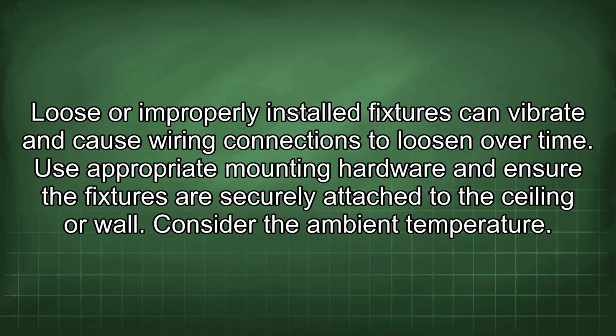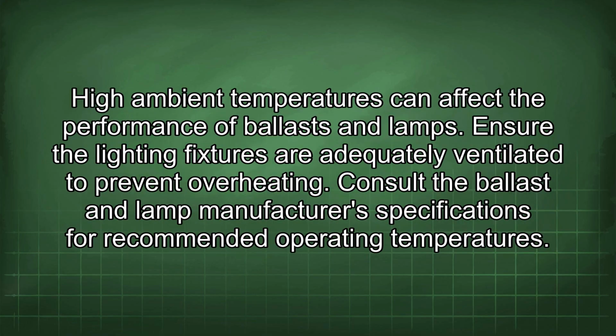Consider the ambient temperature. High ambient temperatures can affect the performance of ballasts and lamps. Ensure the lighting fixtures are adequately ventilated to prevent overheating. Consult the ballast and lamp manufacturer's specifications for recommended operating temperatures.